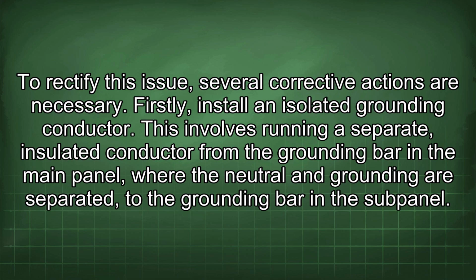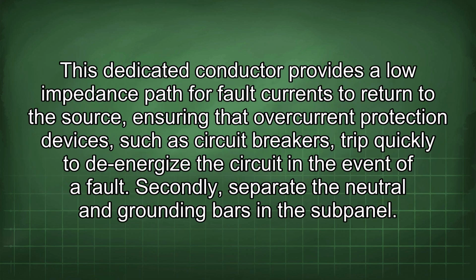Firstly, install an isolated grounding conductor. This involves running a separate, insulated conductor from the grounding bar in the main panel, where the neutral and grounding are separated, to the grounding bar in the subpanel. This dedicated conductor provides a low impedance path for fault currents to return to the source, ensuring that overcurrent protection devices, such as circuit breakers, trip quickly to de-energize the circuit in the event of a fault.